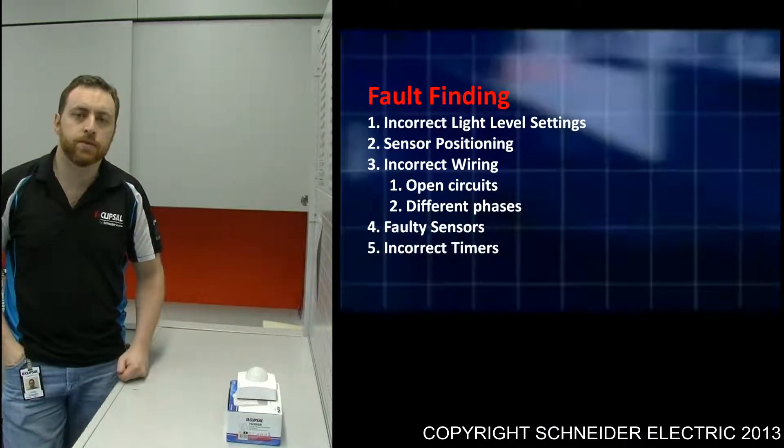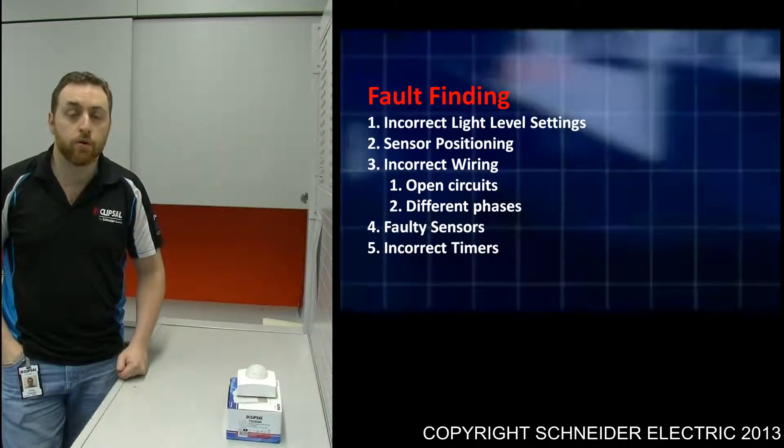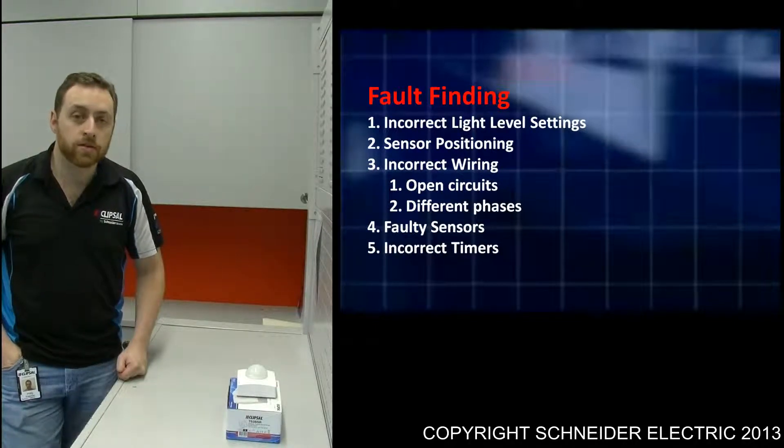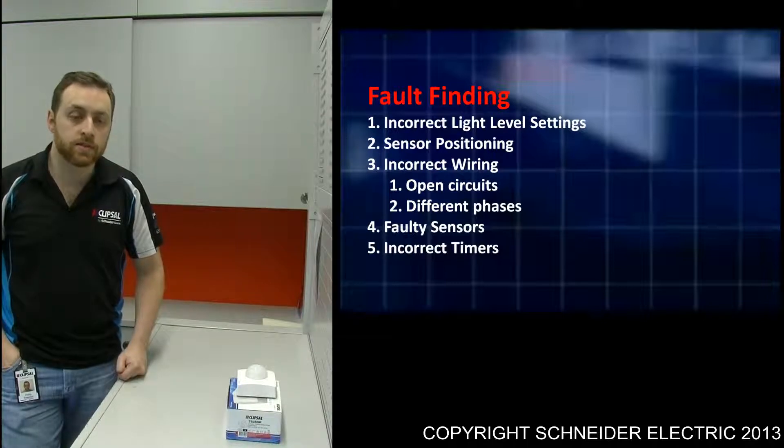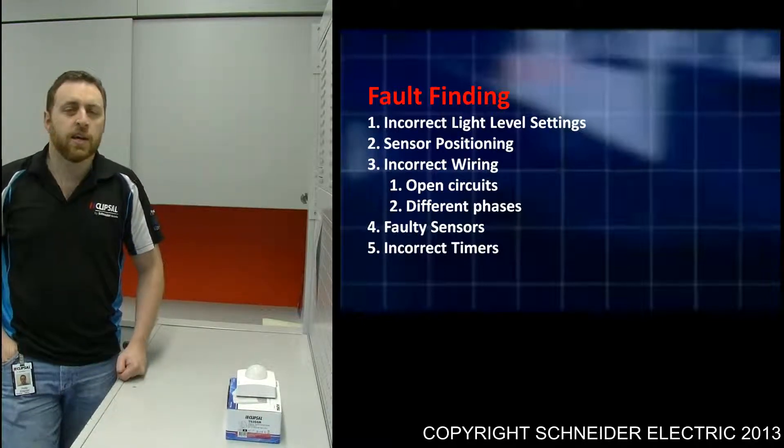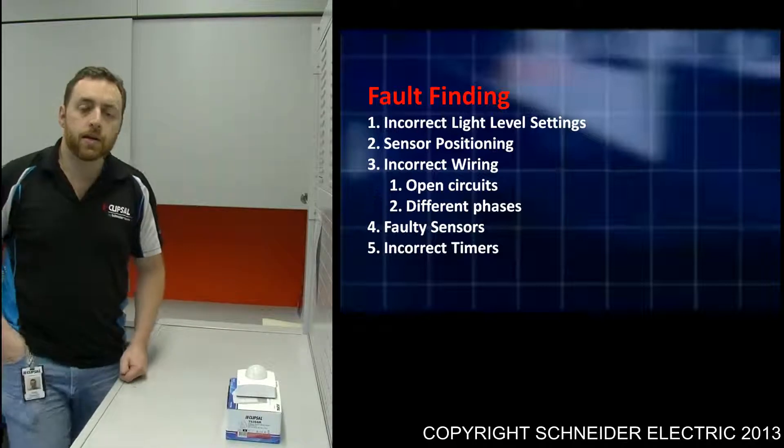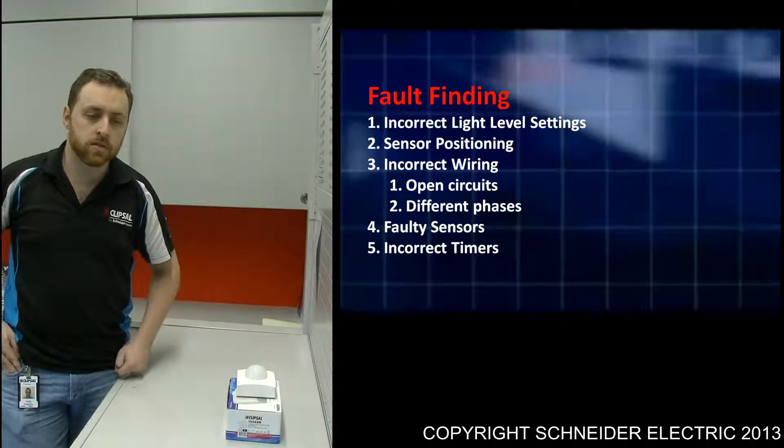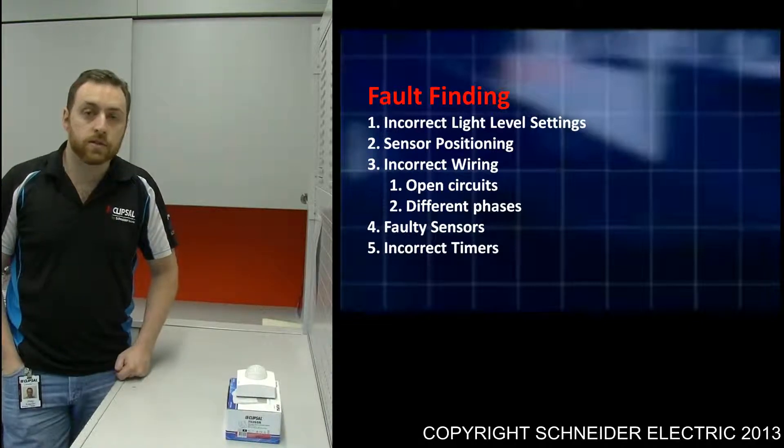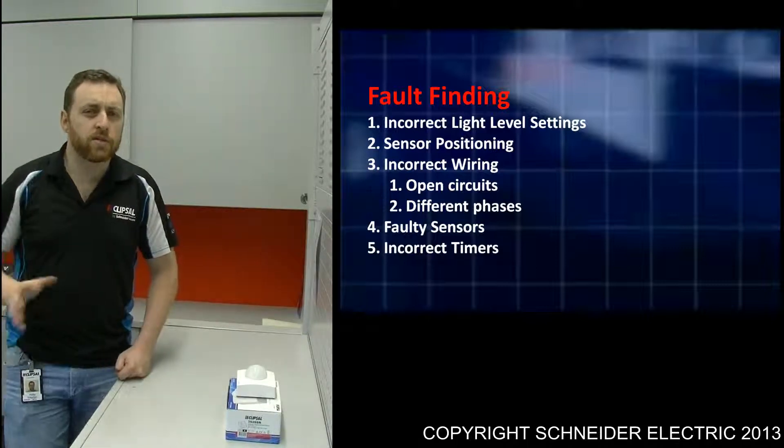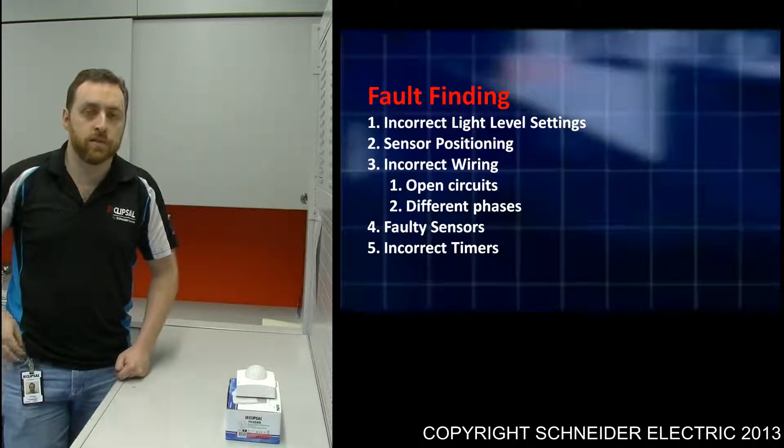If you're experiencing issues on site, some of the more common causes are: incorrect light level settings programmed into the sensor, possibly sensor positioning causing problems, incorrect wiring such as open circuits, connecting multiple sensors controlling one load to separate phases, potentially a faulty sensor, and finally incorrect time settings, which is probably not as common because diagnosing is relatively easy.